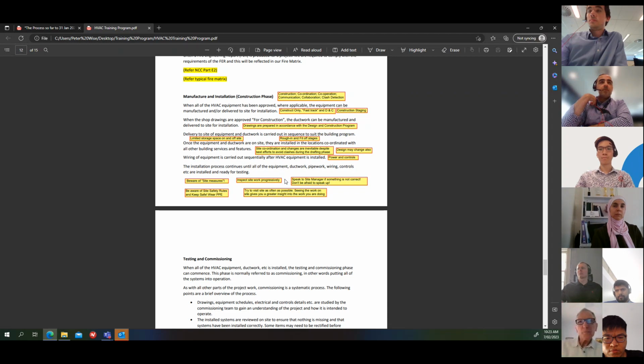So another important thing - it's all important, but particularly the fire safety features, such as fire dampers. Make sure they're installed correctly. Penetrations through firewalls with pipe work - there are requirements for the way pipes are insulated through firewalls. Make sure that's all done correctly, because that can come back to bite you later.